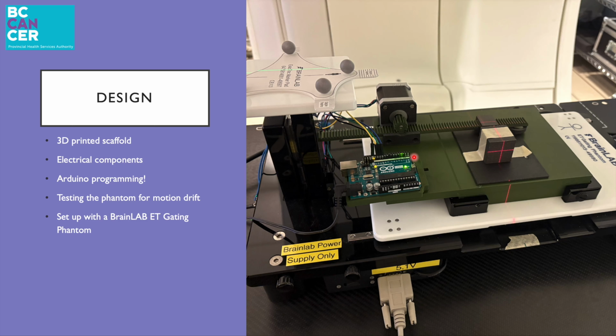This large platform had slots to mount the stepper motor in 3 different directions. However, in this work, only the slot for motion parallel to the respiratory phantom motion was used, and that's the way it's set up here in this image. An Arduino program was written to take an input one-dimensional cardiac motion trace and some set heart rate, and then reproduce that motion. And then all of this was set up in conjunction with this commercial BrainLab ExacTrac gating phantom, which is all the white parts down here. And here you can see the chest plate where we have these infrared markers so that this would move as though it's the patient's chest.